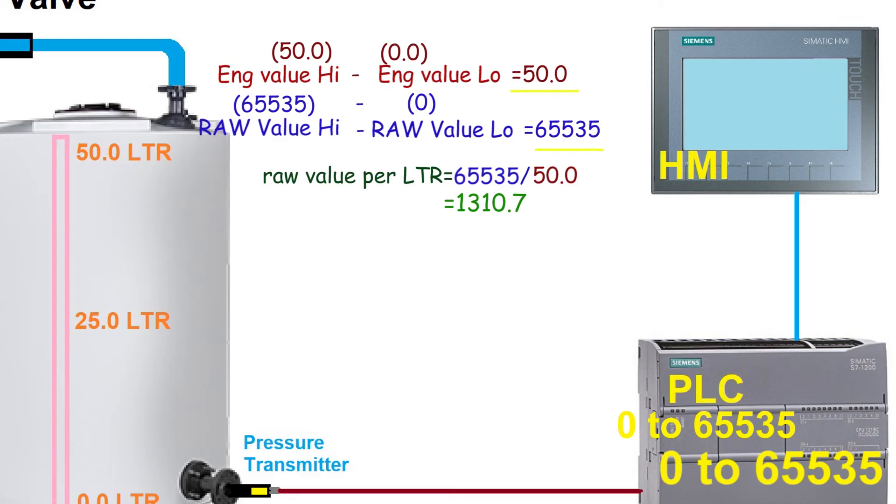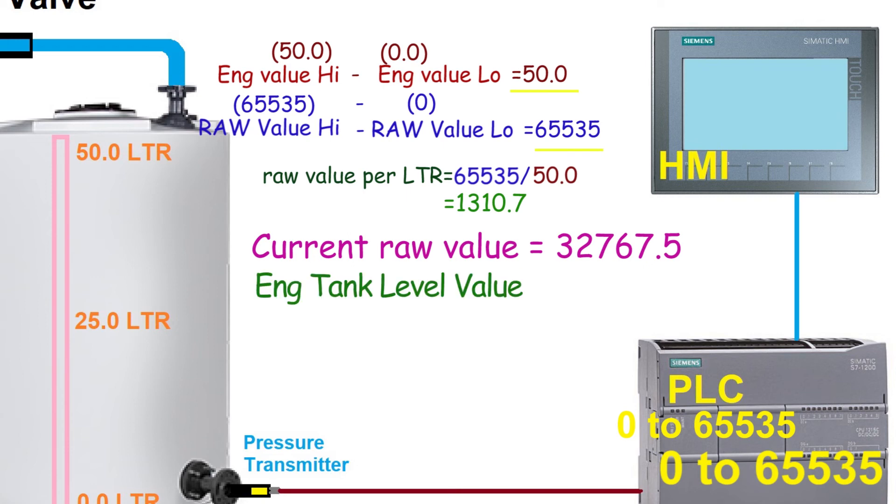Now this value 1310.7 is the raw sensor value per liter of water in the tank. Suppose our raw value is 32767.5, so we will just divide this raw value by 1310.7 and the answer is 25.01 liters. So this is how we can convert 4 to 20 milliamps sensor output to the real engineering value.